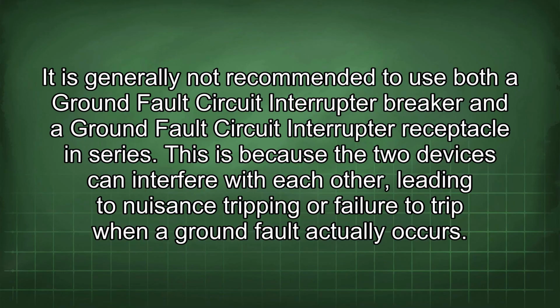It is generally not recommended to use both a ground fault circuit interrupter breaker and a ground fault circuit interrupter receptacle in series. This is because the two devices can interfere with each other, leading to nuisance tripping or failure to trip when a ground fault actually occurs.